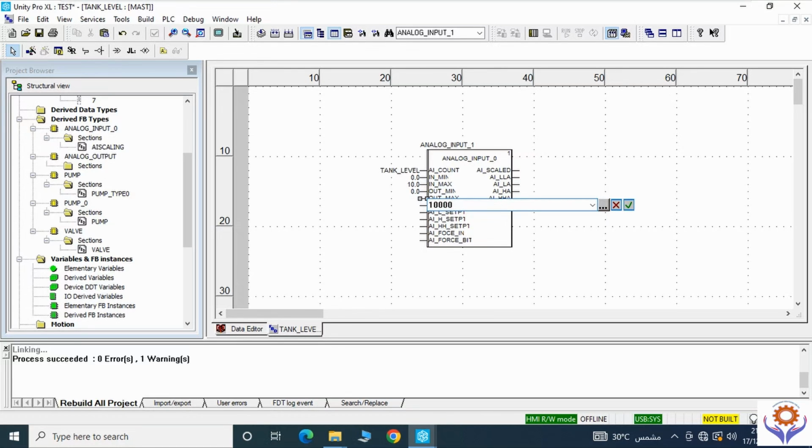And you can set the set point for low alarm, low, high, and also you can force the analog input in this block, and the output will be here. See, whenever you are creating analog input, it will take you here as analog input as integer, and output it will give you as real. So I can add one real value, percentage MW 320.